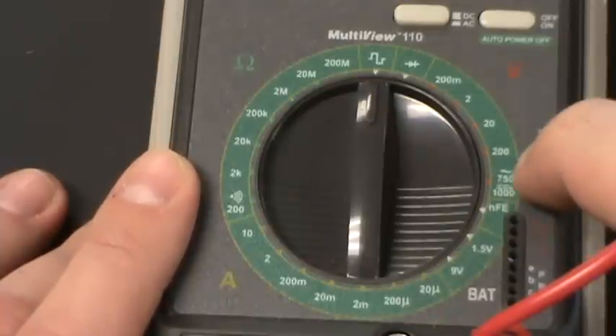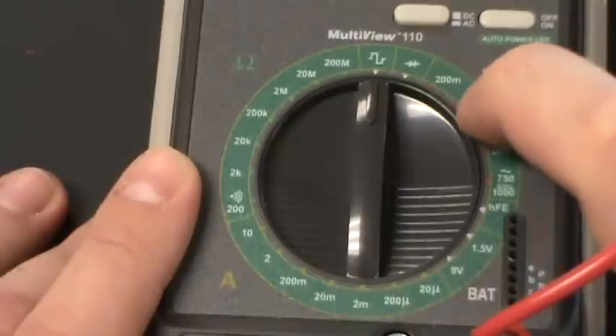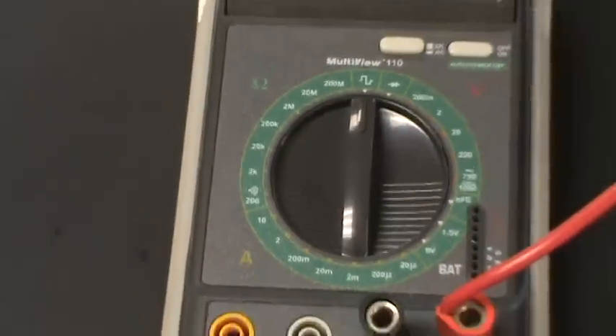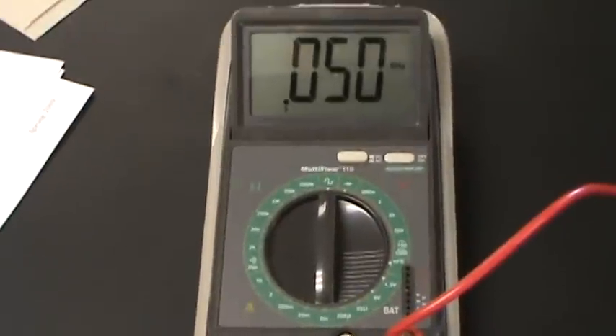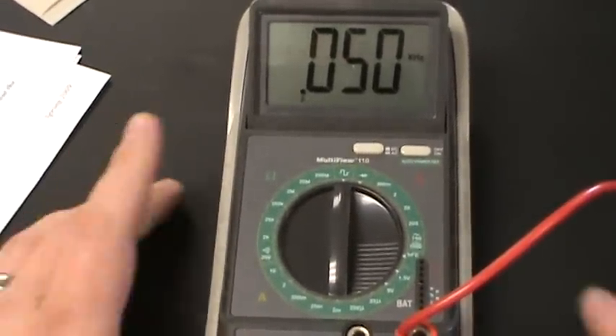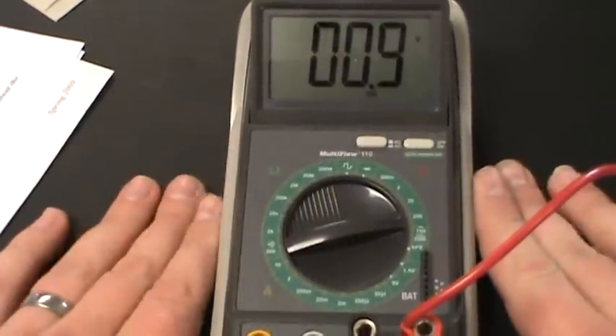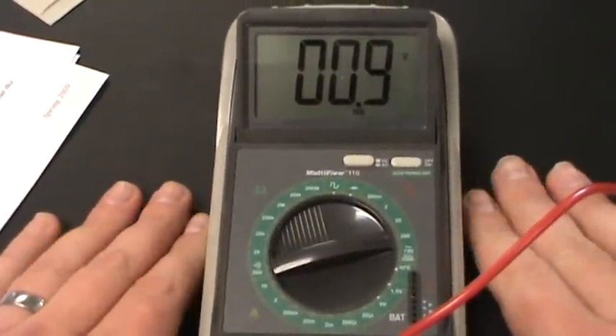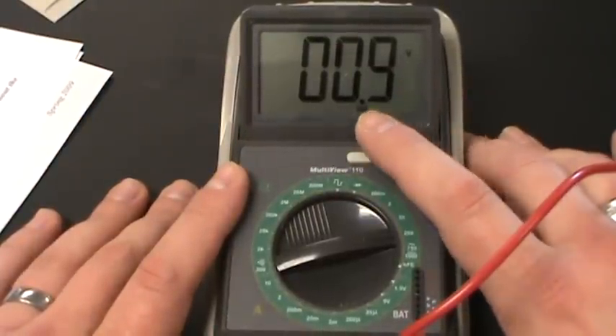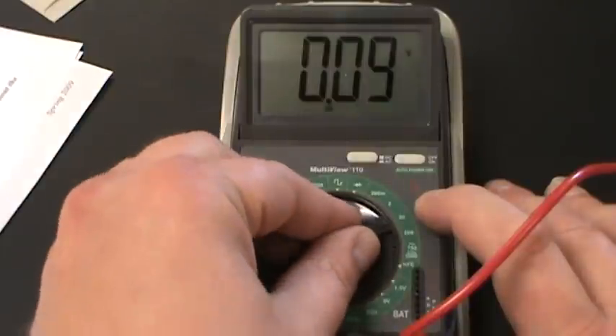But what is this 200, 20, 2, and 200M? Let me zoom out just a little bit so that we can see the display. So if I turn this to 200, it's telling me that the reading is 0.9 on the 200 scale. Well what does that mean?